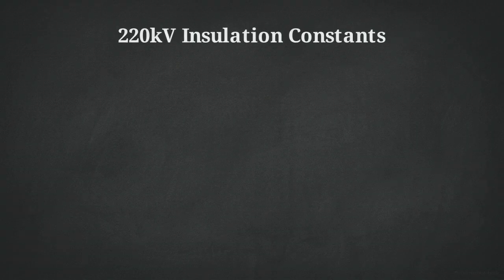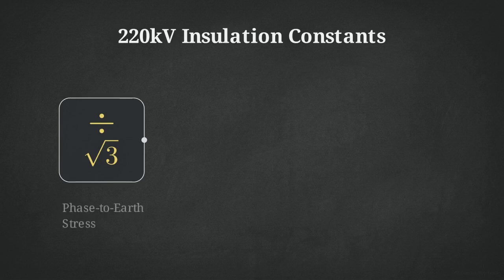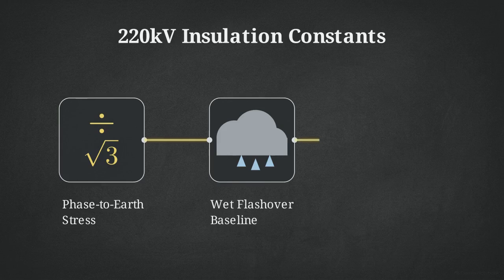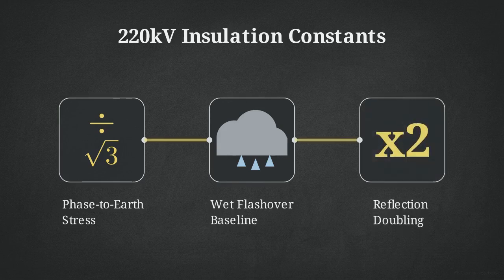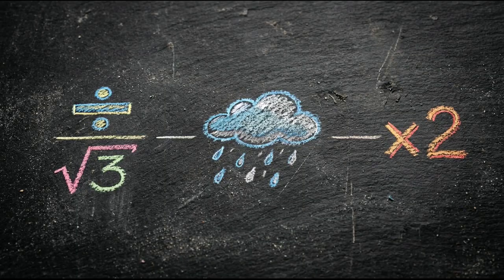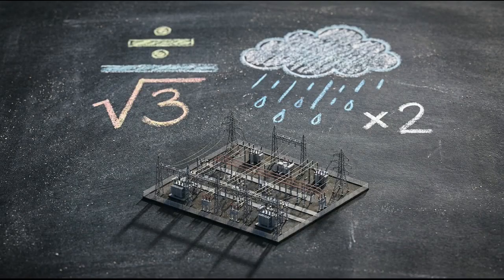Effective coordination relies on 3 technical constants. You must divide line-to-line voltage by the square root of 3 for impulse stress, evaluate the system under wet conditions for sustained overvoltage, and account for the doubling effect of wave reflection. Mastering insulation coordination is about understanding how these numbers represent physical events. By accounting for weather, reflection, and distance, you can ensure that your design provides the exact level of protection required by the equipment.